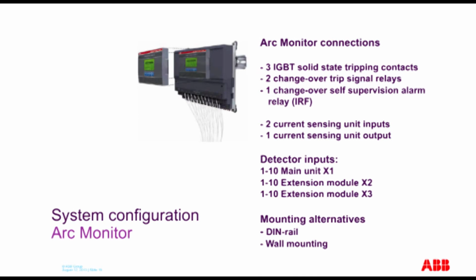So this is, in a nutshell, what the arc monitor consists of. You have 3 solid-state tripping contacts. That means you can trip 3 breakers differently, at different times, depending on where the fault occurs. You have 2 changeover trip signals, which allow monitoring. You can have a trip signal going to, say, a PLC, and another going to a SCADA or DCS monitoring system. So you've got up to 2 changeover trip signal relays.